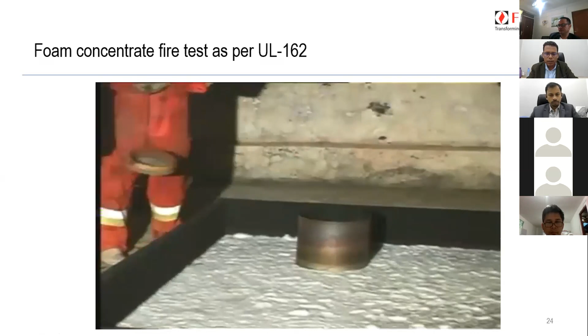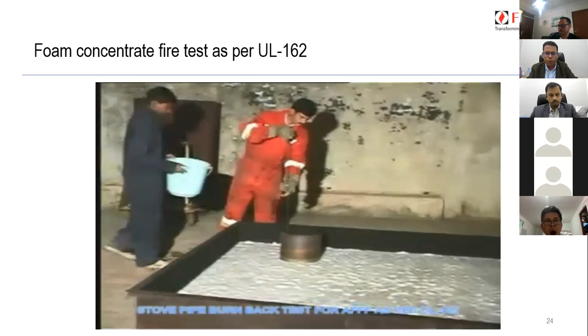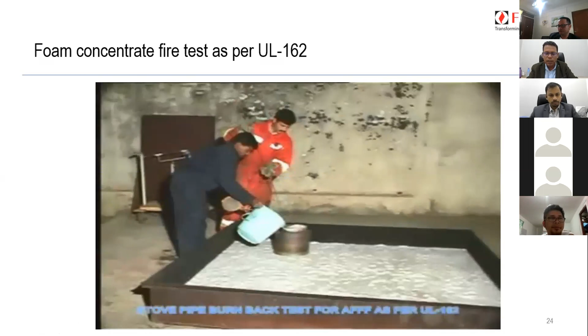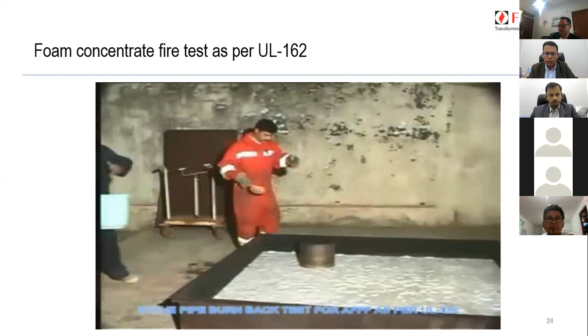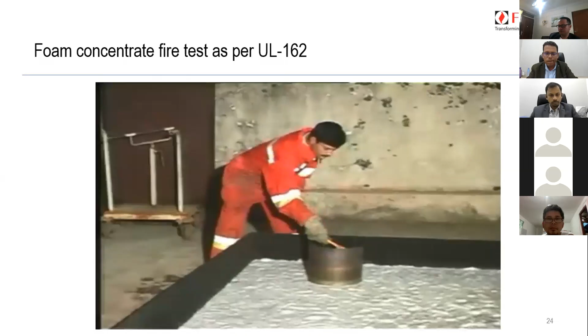And this is a stovepipe testing where a can is kept and the foam is removed from the surface, and that area is again lit with fire to ensure that the foam blanket is not destroyed by the fire in case there is some area open. So this is to ensure the integrity of the foam blanket.